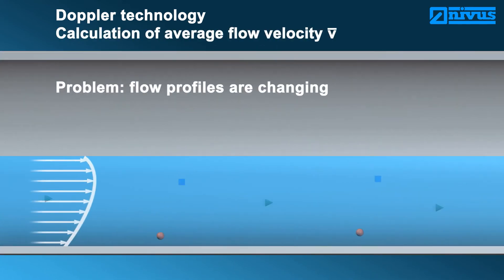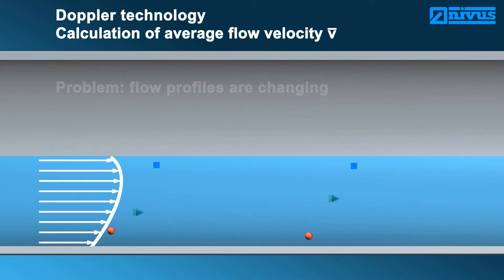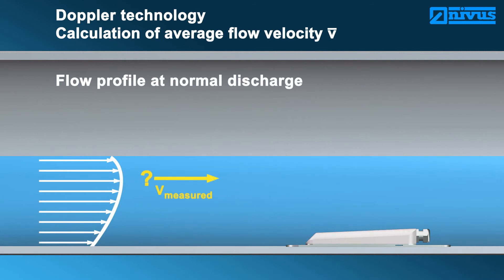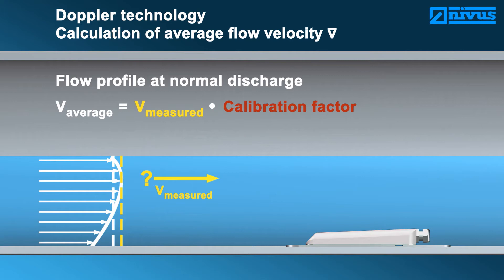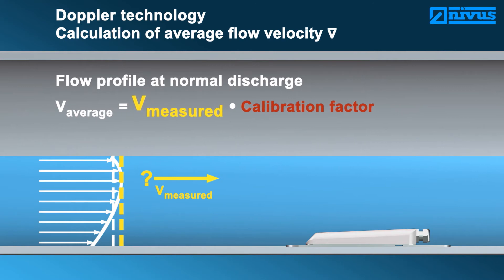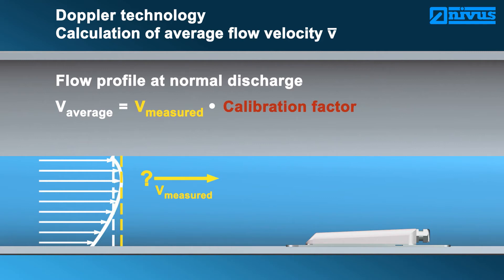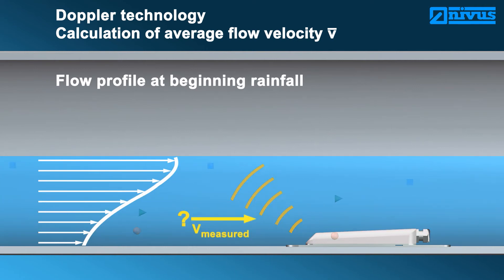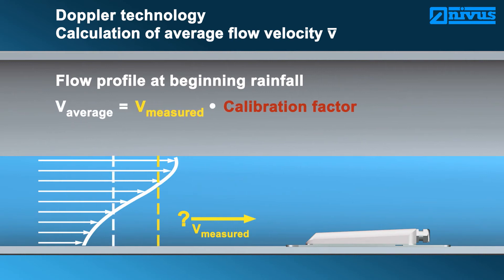The sensor is not able to determine at which level the velocity has been detected. Due to this reason, the flow profile cannot be represented. To counteract this shortcoming, the average flow velocity is computed with the aid of a calibration factor. This factor must be determined previously, such as by implementing a grid measurement, which is fairly time consuming and expensive. The calibration factor is valid only for one stationary condition. If the flow conditions should change, such as due to rainfall, the flow profile will change accordingly, and the originally determined calibration factor is no longer applicable, so the reading is distorted.